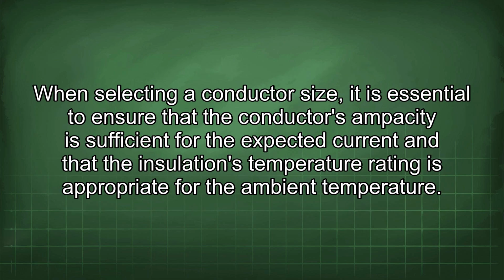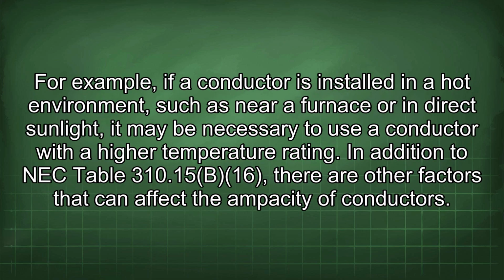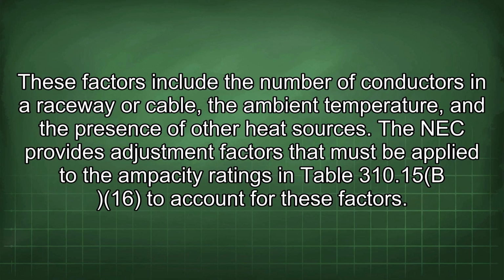When selecting a conductor size, it is essential to ensure that the conductor's ampacity is sufficient for the expected current and that the insulation's temperature rating is appropriate for the ambient temperature. For example, if a conductor is installed in a hot environment, such as near a furnace or in direct sunlight, it may be necessary to use a conductor with a high temperature rating. In addition to NEC Table 310.15(B)(16), there are other factors that can affect the ampacity of conductors. These factors include the number of conductors in a raceway or cable, the ambient temperature, and the presence of other heat sources.